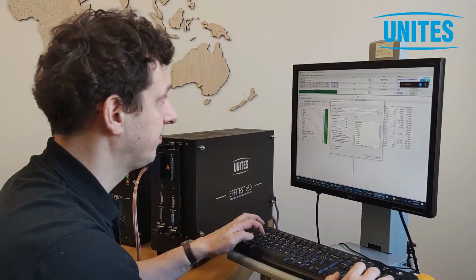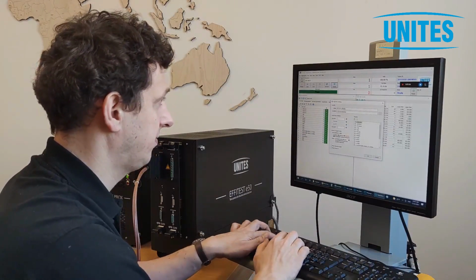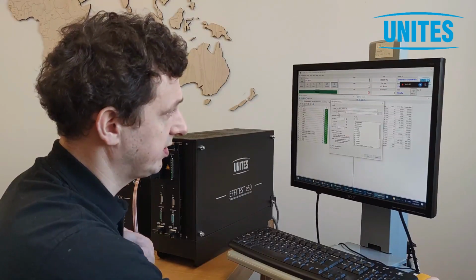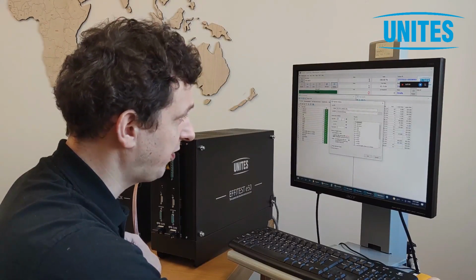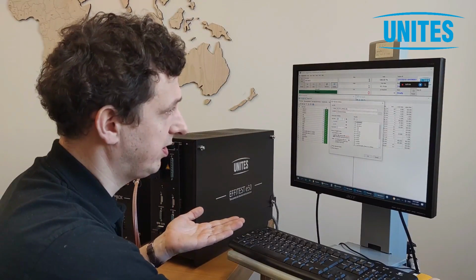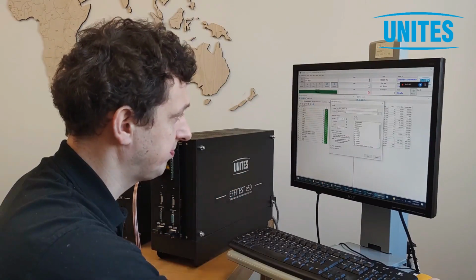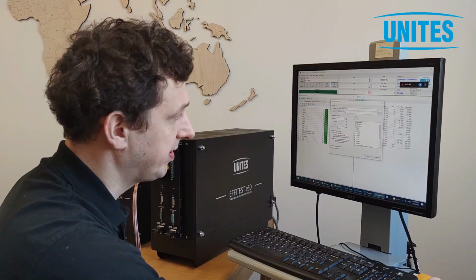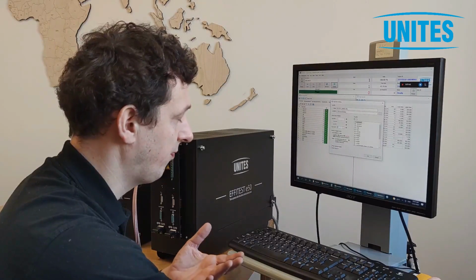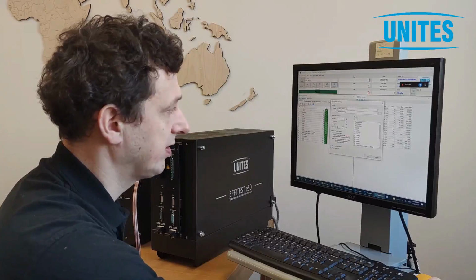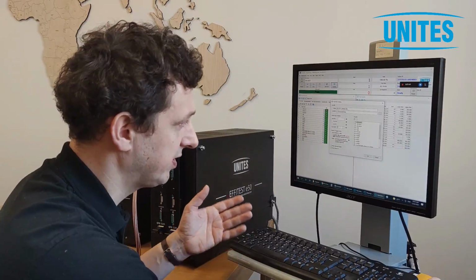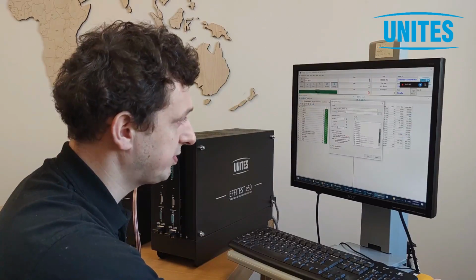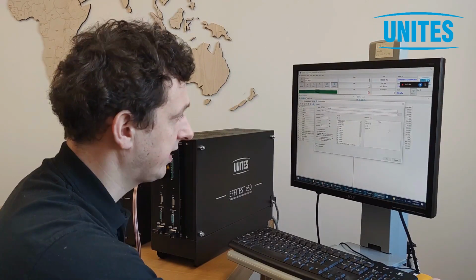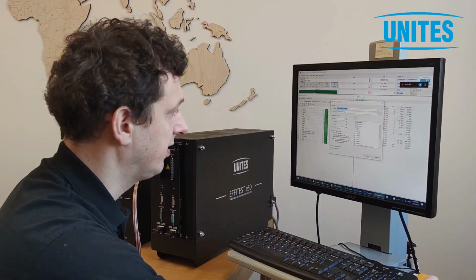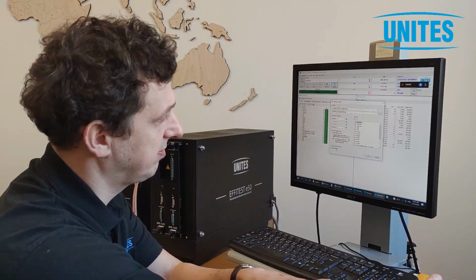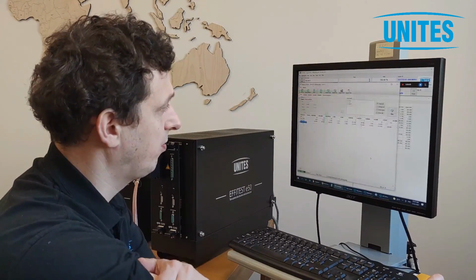So if I put there data log, the name of the data log, they are stored in the data log folder. I can define log rate, which can be each test run, or every second, every third, whatever is there needed. I can limit it if I just want to record few, like 100 first runs, but if I have 0, it's infinite, so it will be always stored. Choose the test steps which will be recorded, and also I can extend it by the operator name, and I can put there a custom device number. So right now I will open the data log.